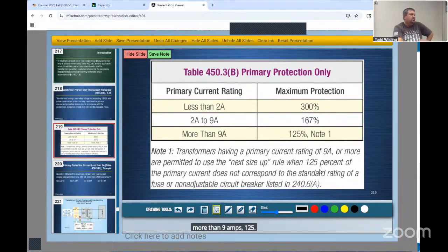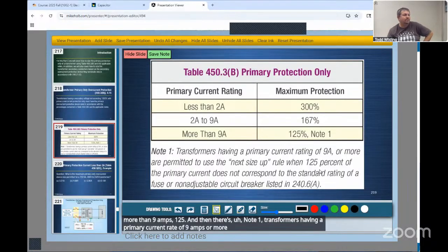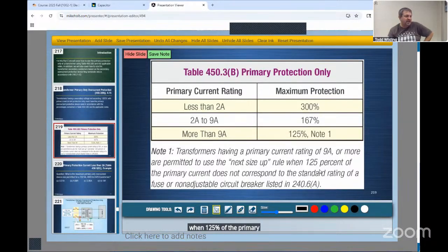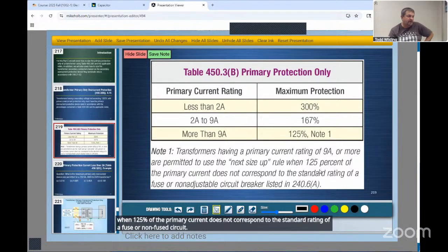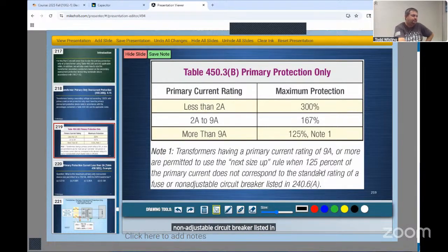Then there's Note 1: transformers having a primary current rating of 9 amps or more are permitted to use the next size up rule when 125% of the primary current does not correspond to the standard rating of a fuse or non-adjustable circuit breaker listed in 240.6(A). So what does that say? If I'm using 125% and say I get 32 amps, what size breaker or fuse can I use?